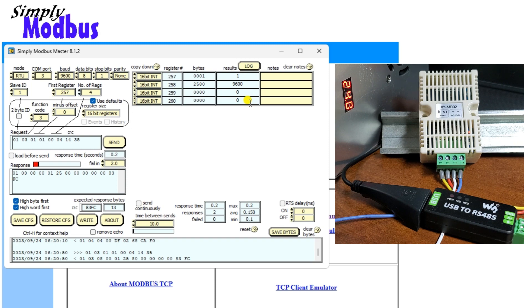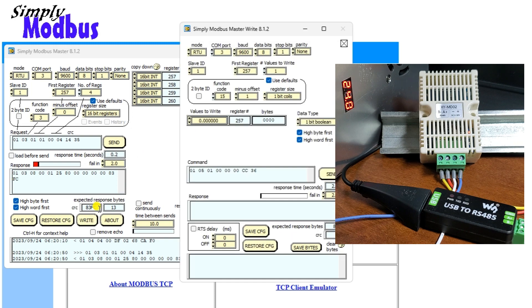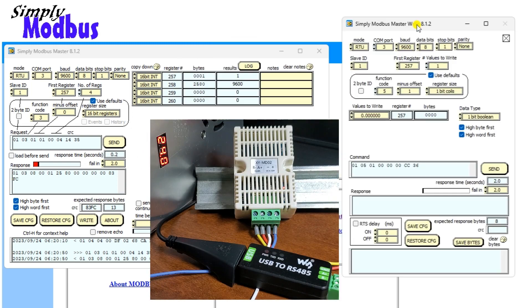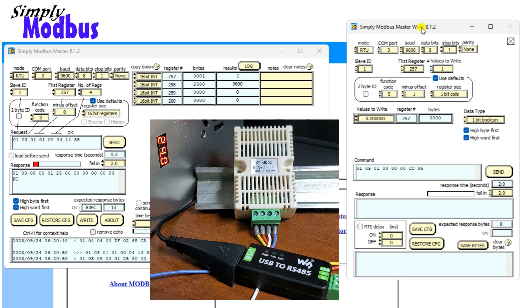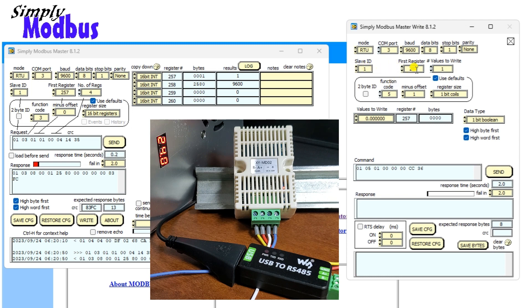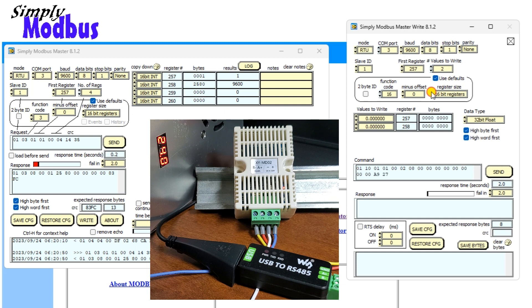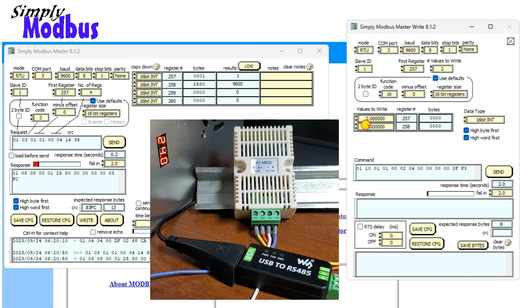Select the write button. The Simply Modbus master write window will now be displayed. We will change the Modbus unit number and the baud rate. The first register will be 257, which is 101 hex, and we will write two 16-bit addresses. Function code 16 or hex 10 will be used to perform the write operation. Enter the values for both registers and select send. This will now set the new parameters into the sensor.